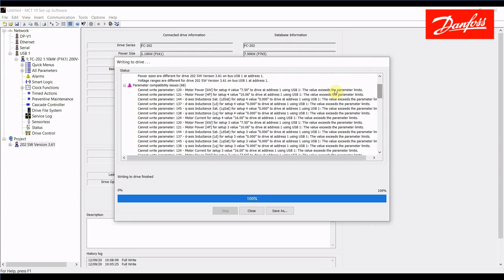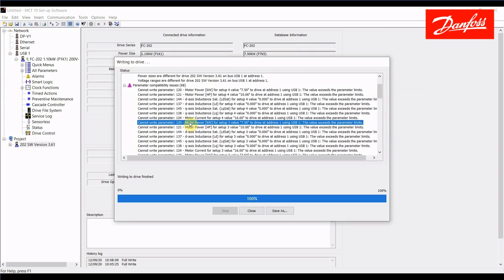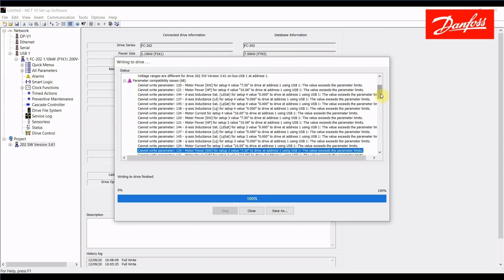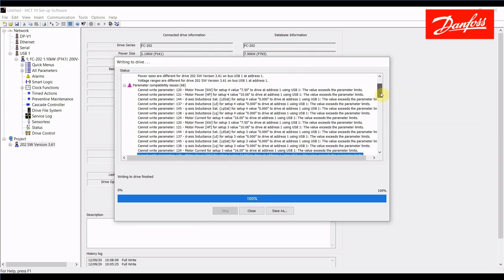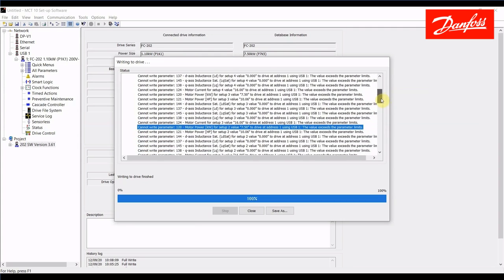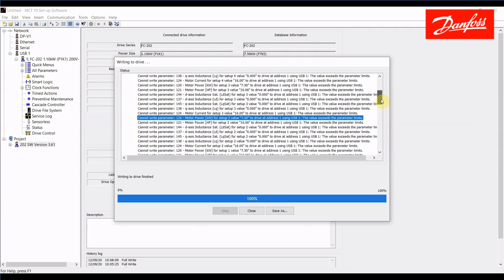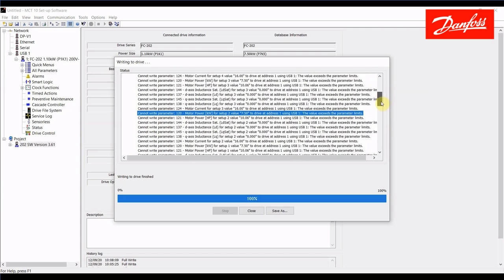It does appear longer than it actually is because it's listing the same parameter for all four setups. So for example here it can't write this parameter 120 in setup 4, setup 3, setup 2, etc. So everything is actually listed four times. All these one group parameters are related to the motor data and I'm not concerned about those because I'm going to go in this drive I've written to and adjust the motor parameters and do a motor tuning anyhow. So those will all be addressed automatically.